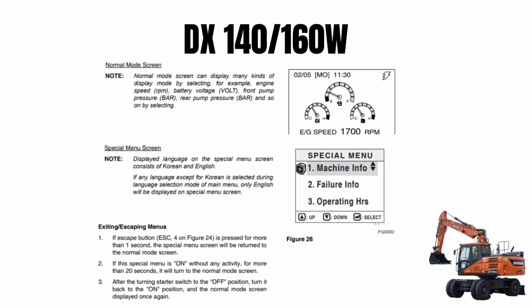Special menu. I already told you it consists of 3 sections: machine information, failure information, and operating hour. Exiting and escaping the menu: if the escape button is pressed for more than 1 second, the special menu screen will be returned to the normal mode screen.